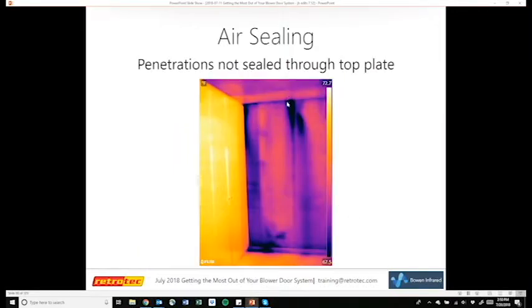Here's another one where we have electrical penetrations through the top plate. You can see it's right alongside the stud. Even on this side, the exterior air is coming down through those small penetrations and flowing along the drywall on both sides, where they've got a hole drilled for the electrical wiring and it wasn't sealed correctly. We also have some airflow along the bottom plate that's not sealed to the subfloor. That's quite common, but we're trying to emphasize this air leakage that can occur and visualize it with a thermal camera.